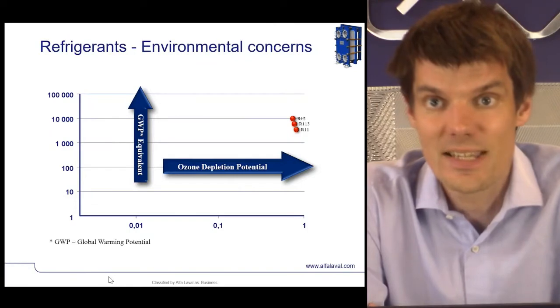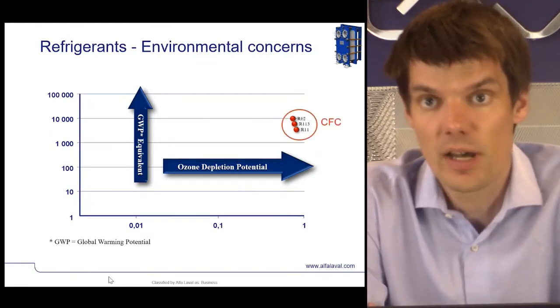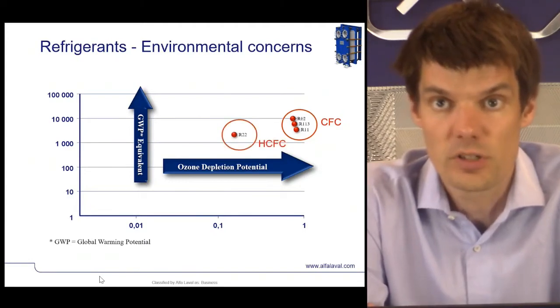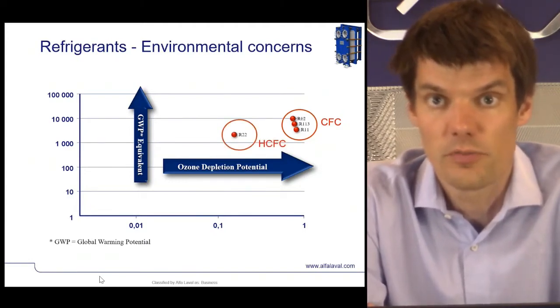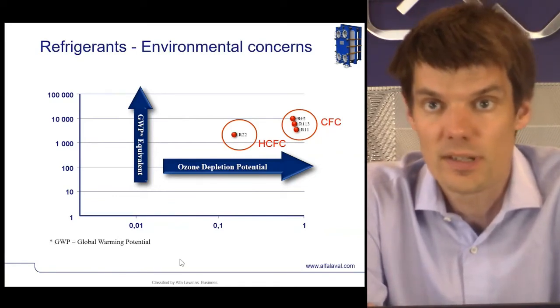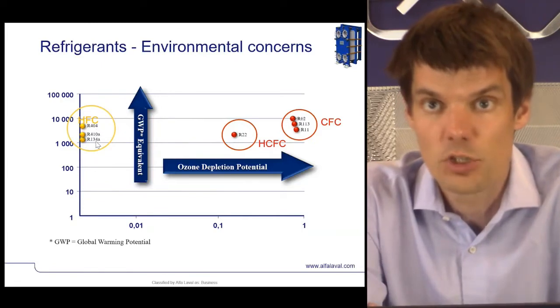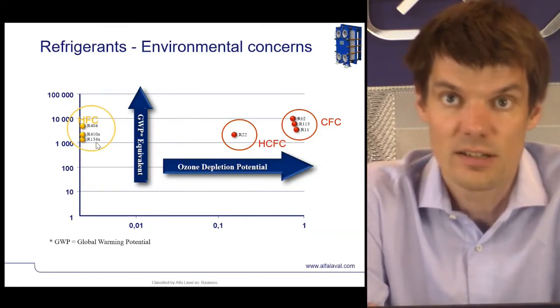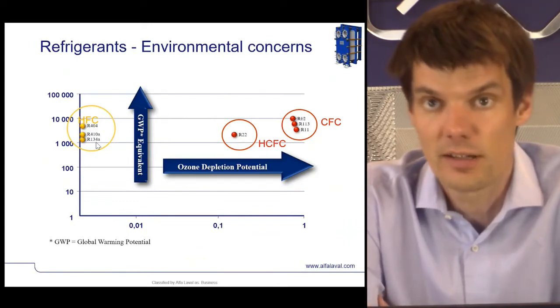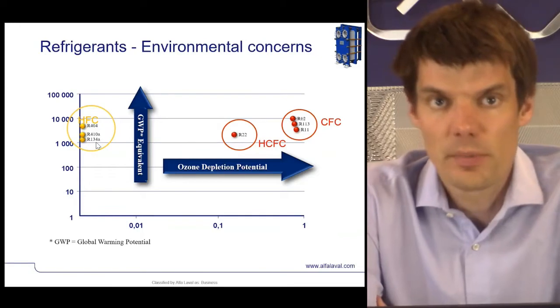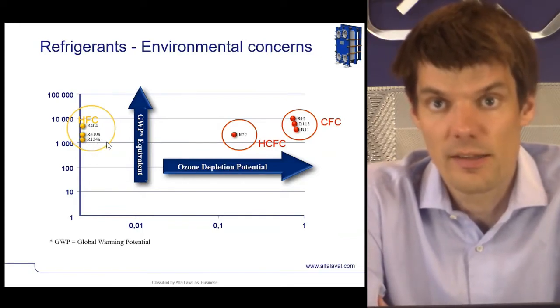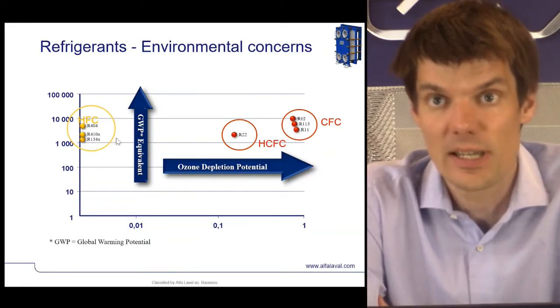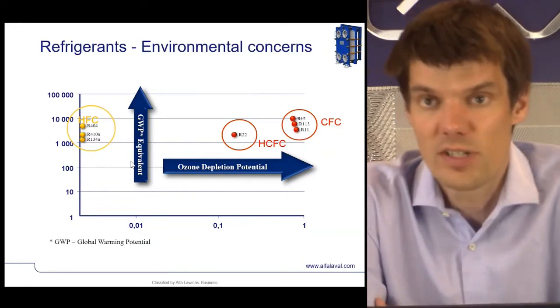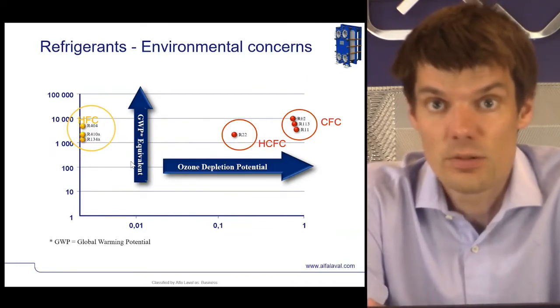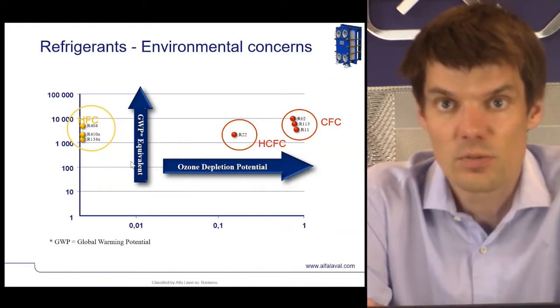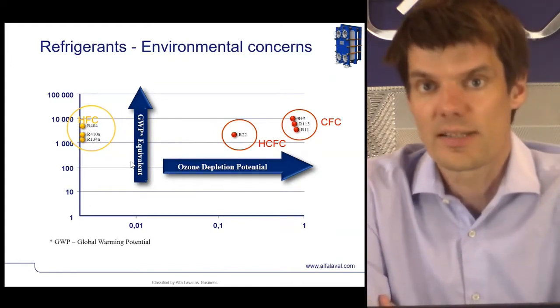The really old so-called CFCs and HCFCs, freon, had a very high ozone depletion potential. Therefore, it was decided through the United Nations Montreal Protocol to phase out these refrigerants and replace them with something less harmful, the HFCs, which is the refrigerant that we are seeing in today's HVAC chiller and refrigeration applications. The problem with these refrigerants is that they have a very high global warming potential. Simply, they are much worse to use than releasing CO2. Therefore, it has been decided to phase out these refrigerants as well, replacing them with something else.